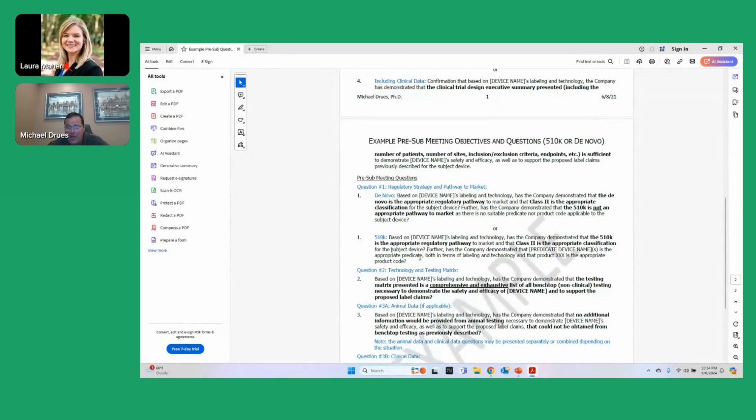There's a big difference. And one other thing that I want to point out, to justify what I'm doing as well as what I'm not doing. Look at the de novo example. Here's a question that I use in most of my de novo pre-subs: based on the device's name and technology, has the company demonstrated that the de novo is the appropriate regulatory pathway, class 2 classification, and so on? Further, has the company demonstrated that the 510K is not the appropriate pathway to market, as there's no suitable predicate or product code? Here is an example of how I'm justifying what I'm not doing and why I'm not doing this.